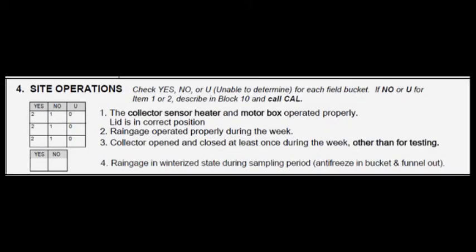Once cleaning is complete, verify correct operation of the equipment, including the rain gauge, motor box, and optical sensor. Be sure to check the connections and inspect the equipment. If you notice any issues, report them in Block 10, Remarks, on the field form, and if necessary, contact the CAL.